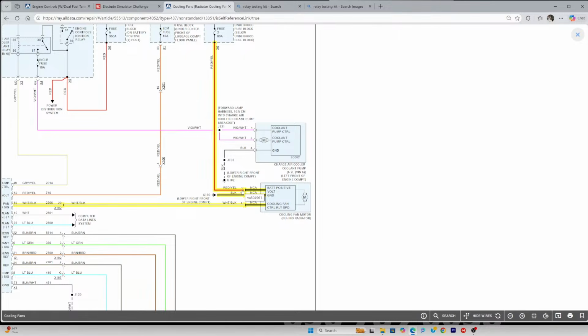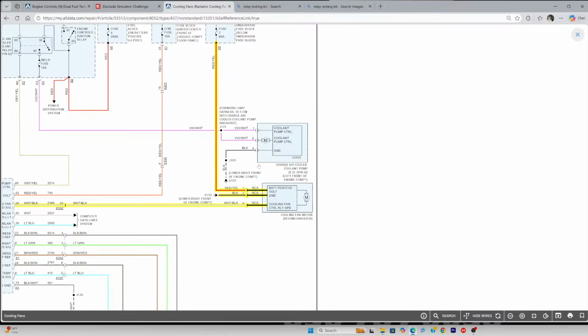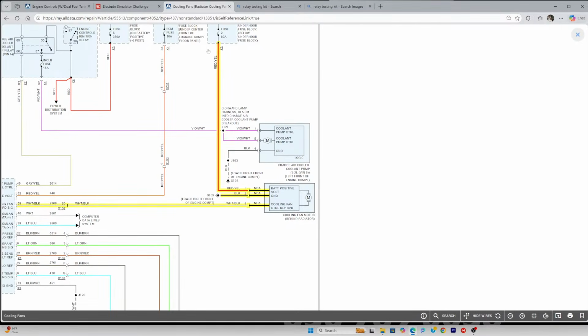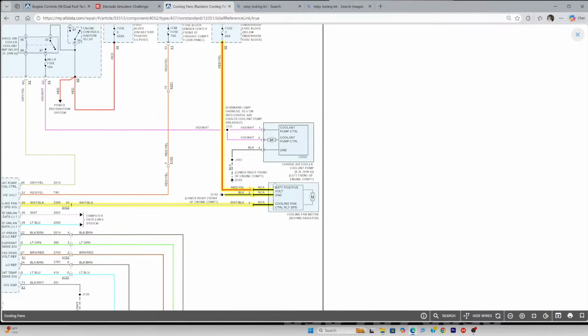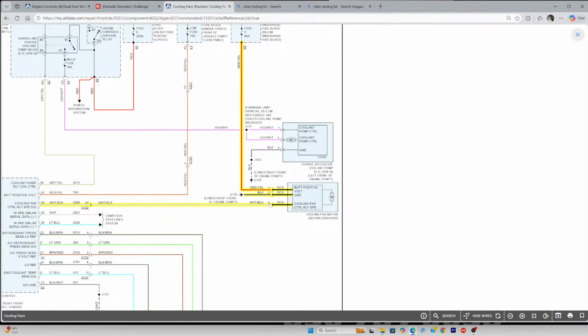Those are some rare cases that we get. So check for your fuse, make sure you have a good fuse right here, and good voltage. If we're reading a low voltage code, that means we don't have voltage here, or we have a short to ground. So number one, check for voltage here. Nonetheless, you want to check for good ground here and good voltage here.